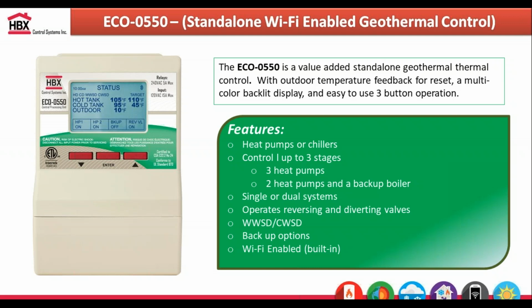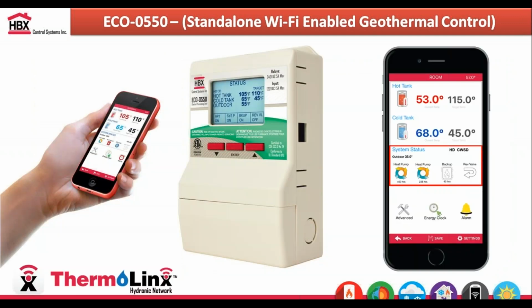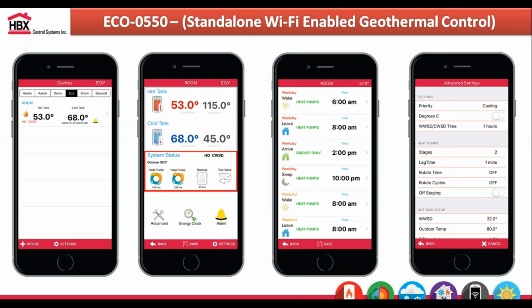Anything 3 stages or less, you want to go to our Eco 550. Again, 3 heat pumps on and off, or 2 heat pumps and a backup boiler option. Again, we can do single or dual tank systems for hot or cold tanks, all with outdoor reset. Operate reversing valve, and we do have that built-in Wi-Fi communication on the Eco 550 in terms of getting alarms for your hot tank or cold tank, or if the contractor wants to log in to adjust any settings, he has the capability of doing that with the Eco 550. So again, navigating through the app, you can see what devices are on and off.